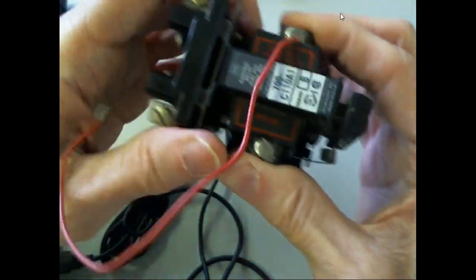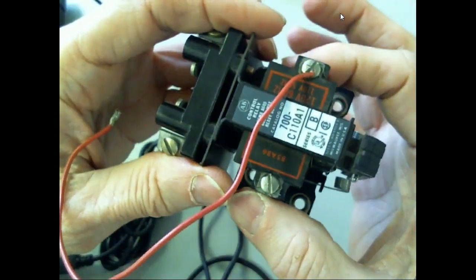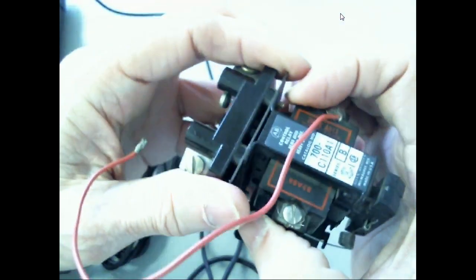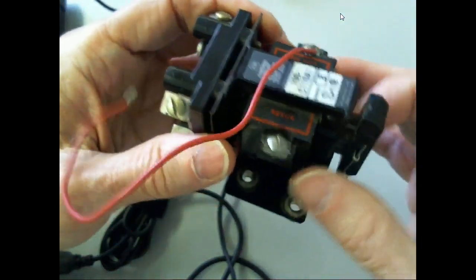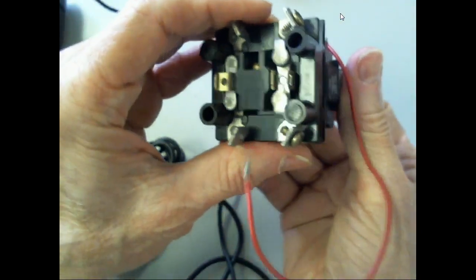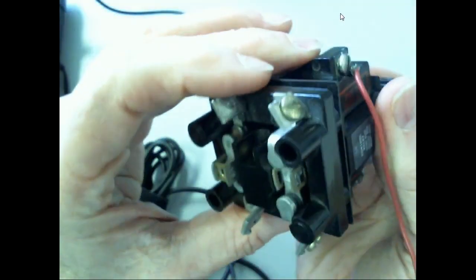back out, right? Some relays don't have that, guys, and they depend on gravity. So for a relay with a gravity return, you've got to make sure you mount it like this, right? You understand? If you mount it like that, the first time it energizes, it's not going to de-energize, right? So here's the solenoid right here. Here's the coil for the solenoid. Here's the solenoid, this whole thing right here. And then the armature goes up and does what? It literally makes and breaks contacts.